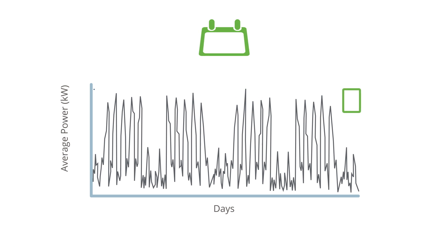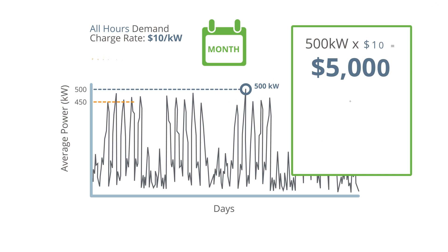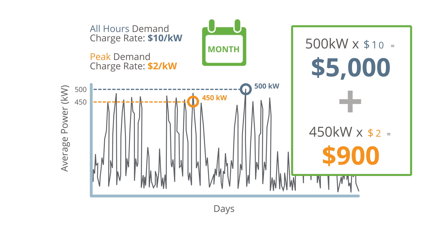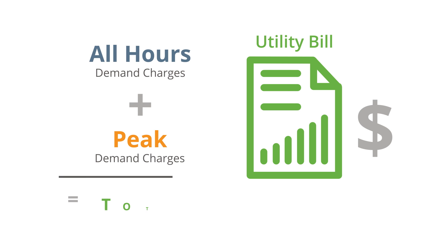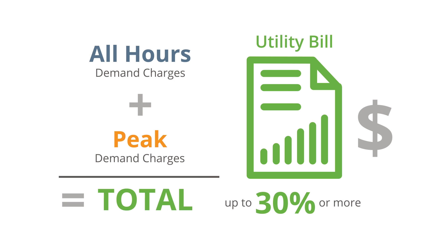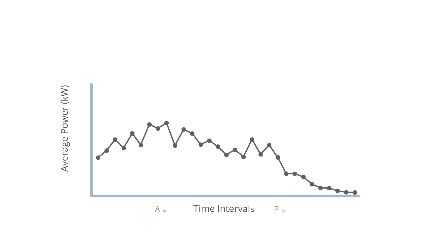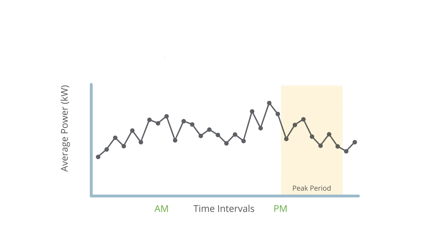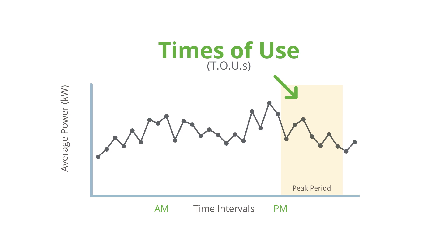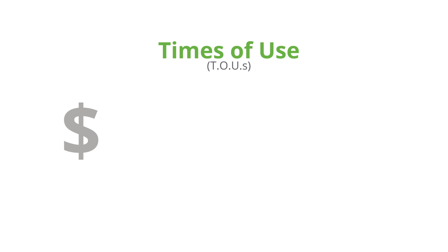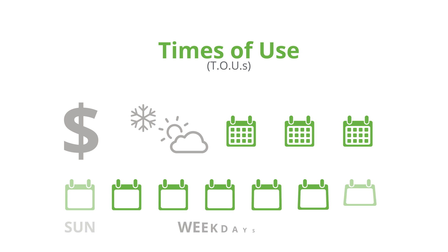Revisiting the billing cycle, on top of the all-hours demand charges, additional peak demand charges would be added. This means the total demand charges equal all-hours demand charges plus peak demand charges, which can add up to a significant portion of monthly energy costs. Now let's look at times of use. The peak period mentioned earlier is what's known as a utility time of use, or TOU. TOUs are periods defined by the utility with different rates and pricing, and in addition to affecting demand charges, they also affect energy prices. TOUs vary by season and even by type of day, like weekday or weekend.